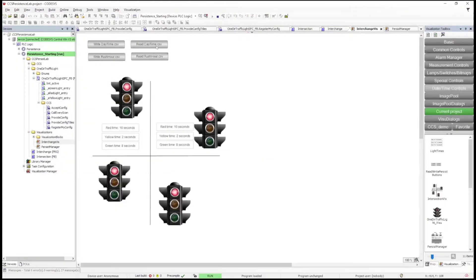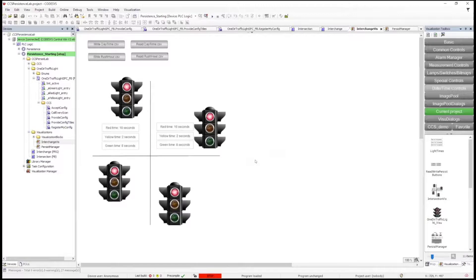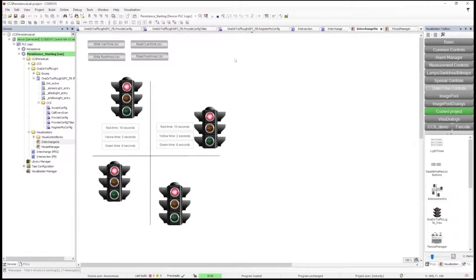Then we just come back in and tell it to read. We could either do an online warm reset, which automatically reads the CSV file, or we could say read the CSV file — either way works. And then you'll notice the lights will now begin to work properly after about 10 seconds. Now they're working properly because they've been configured.